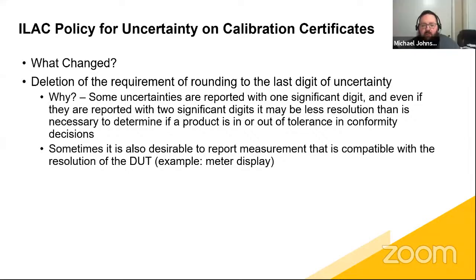There were a couple of questions about Metcal and how it handles this, and I'll address those myself. For those not aware, I'm the product owner of Metcal. The specific question is about how it handles the change, since previous guidance from Fluke was to set the resolution to a high number so you could use that for your CMC. The guidance we've given, which is also an article on our knowledge base, is basically covered by what Jeff talked about in note 3, using a zero repeatability.